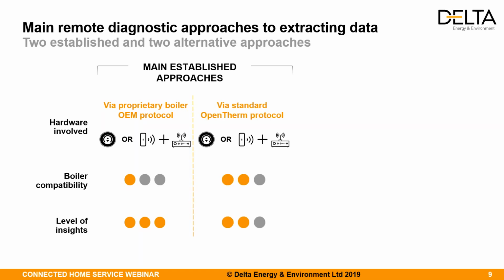Then another established approach is using the OpenTherm protocol, which is quite common in some markets, but overall its penetration is fairly low in Europe. There's big penetration in the Netherlands, for instance. This allows for much wider boiler compatibility, so any boiler really using the standard OpenTherm protocol.